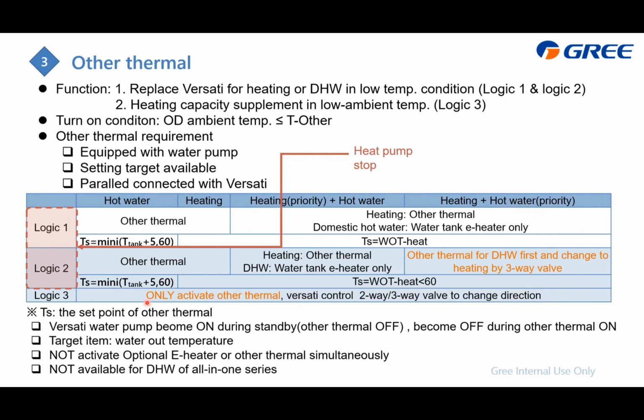As for the logic 3, it only activates the other thermal, and the VERSATI will control the two-way or three-way valve to change the direction, which means this one is acting as a supplement. And also, please pay attention to this T set, and it has the relationship with the T water setting temperature. And on the other hand, please do not activate the optional heater together with this other thermal. And also, this one is not available for the all-in-one series for the DHW.